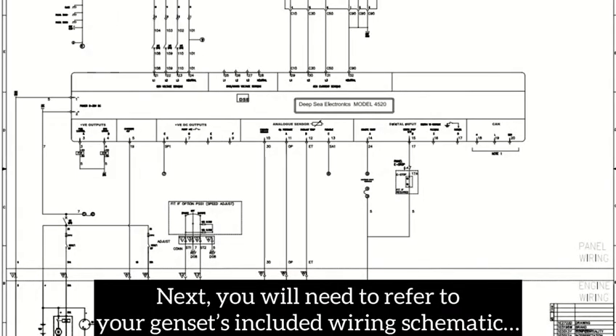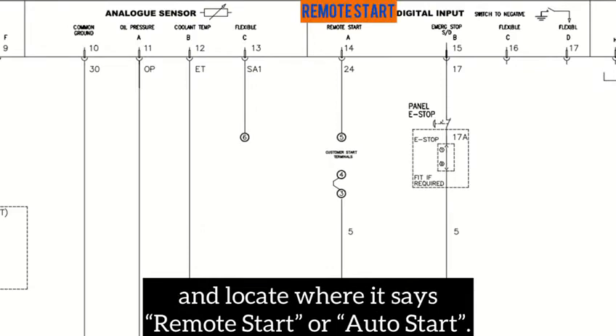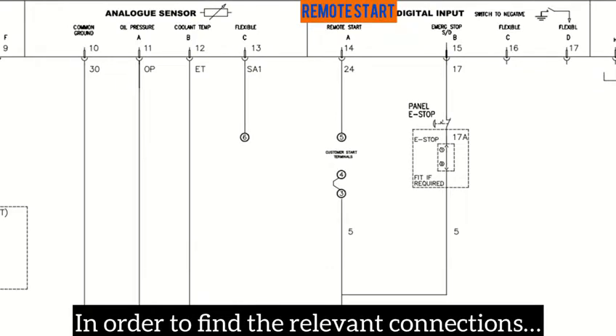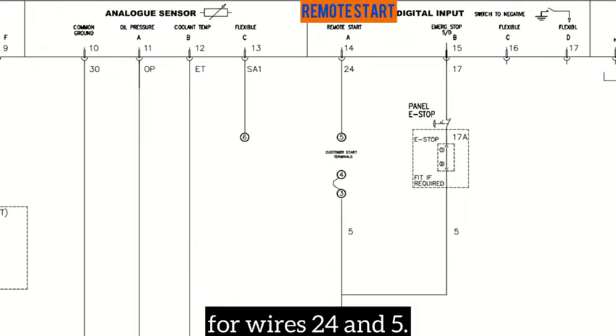Next, you will need to refer to your genset's included wiring schematic and locate where it says remote start or auto start in order to find the relevant connections for wires 24 and 5.